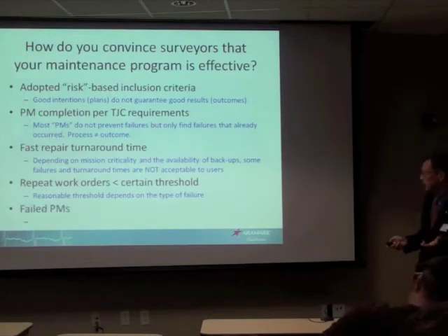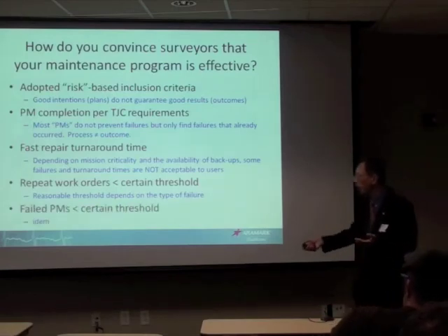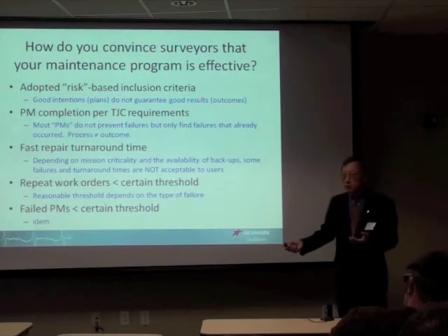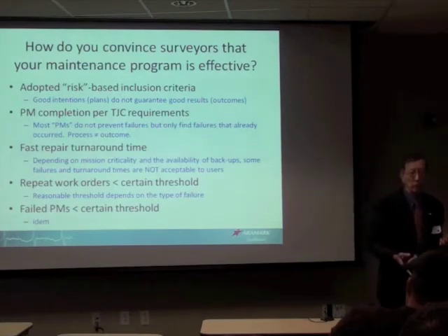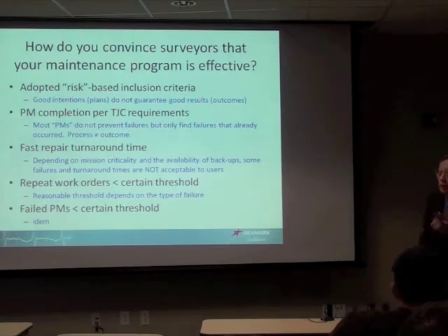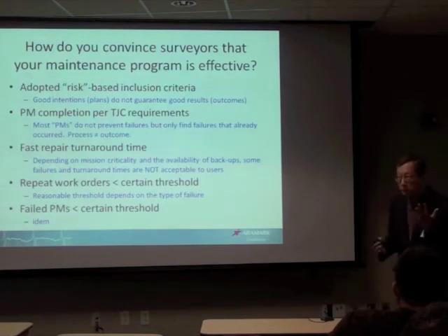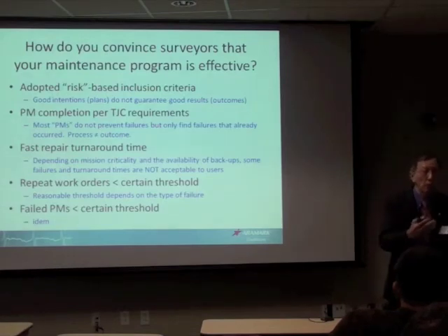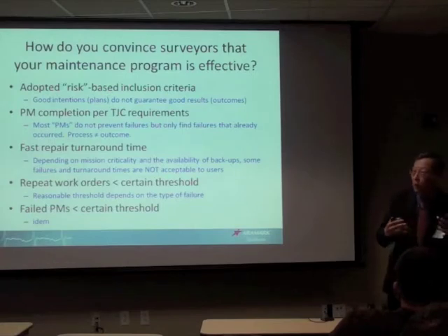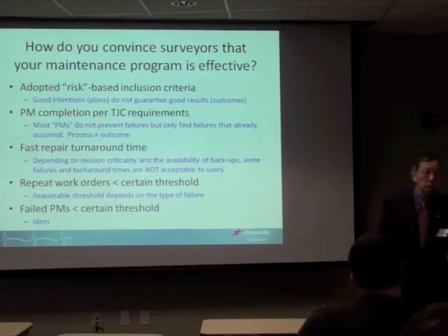Likewise, it depends what you call failed PMs, like the discussion we're having. One to two, depends on what kind of failure. If you have one critical failure to a PM, that could be very important. But if you have five failed PMs due to electrical safety on a ventilator, or even an infusion pump, it's not that critical.